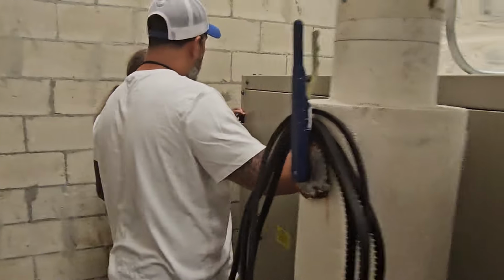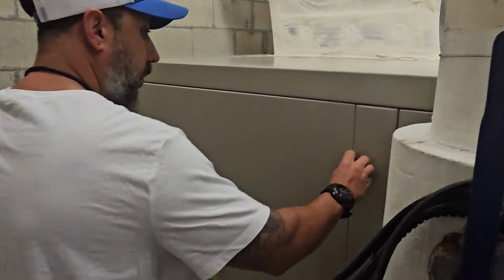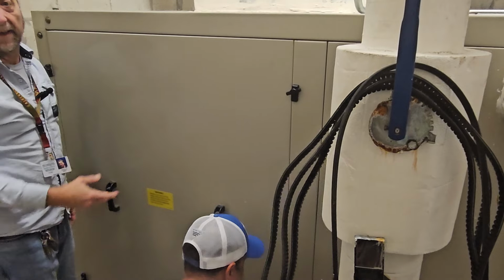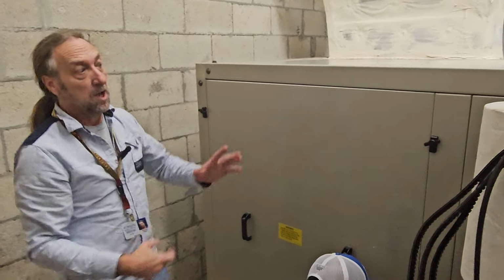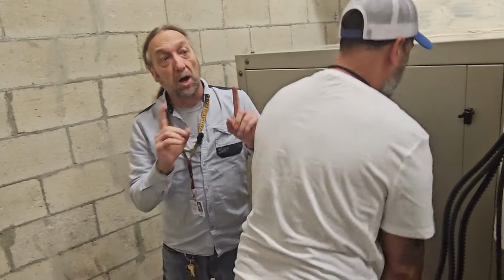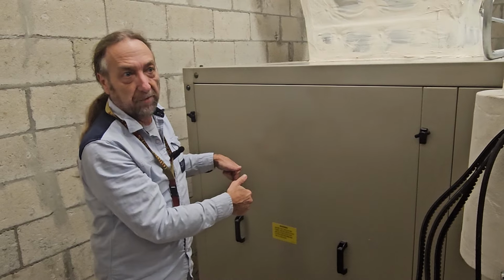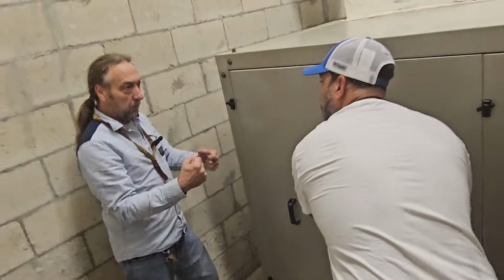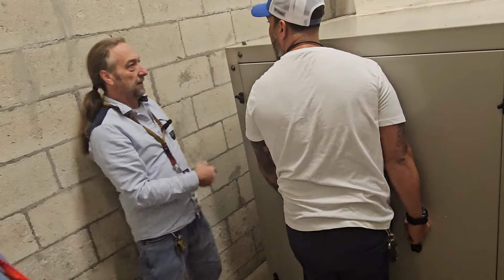Okay, I need some help here. Just loosen. Look, loosen and then turn. Now, the reason I say I need help, because it's going to take two hands to pull this because of the fan. The fan suction is so strong. We're going to see the evaporator in here, but unlike our refrigerators or ACs, the evaporator doesn't have Freon. The evaporator is just cold water. The machine we saw makes the water cold, and the cold water comes here. So if we have a leak, we're going to have water. That's it. So come here. Come on, pull.